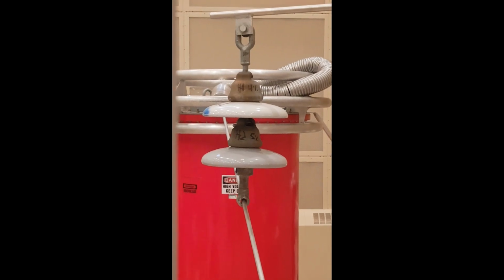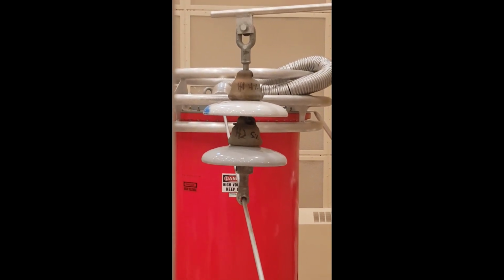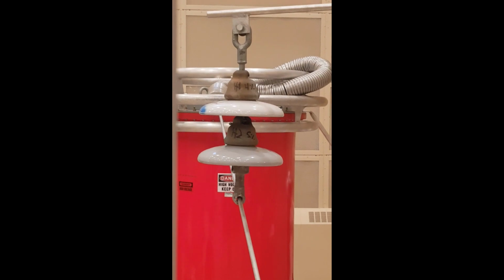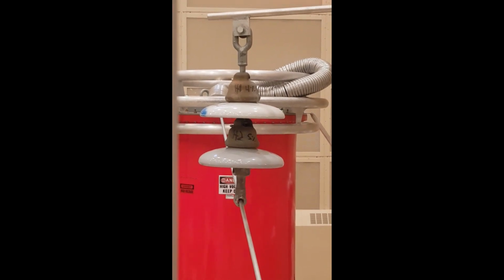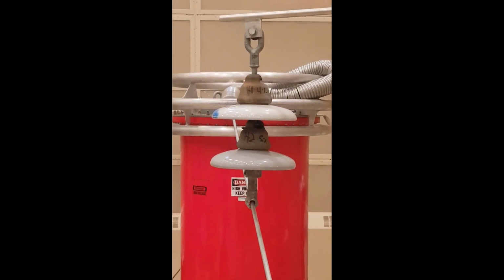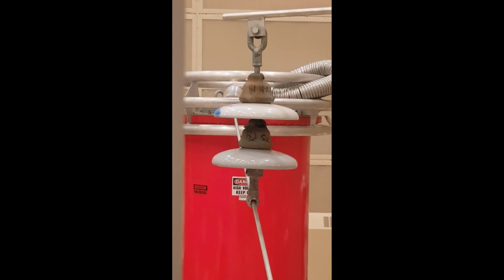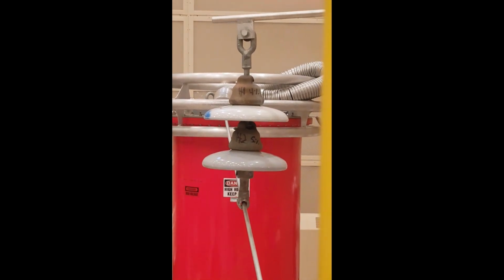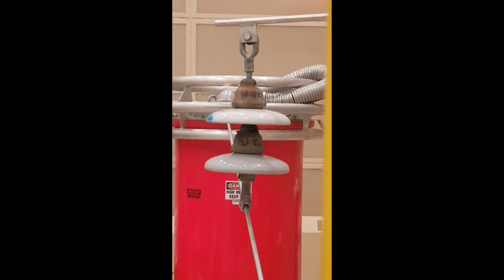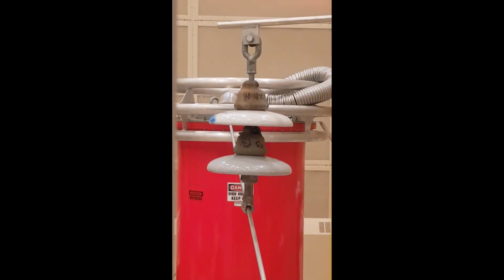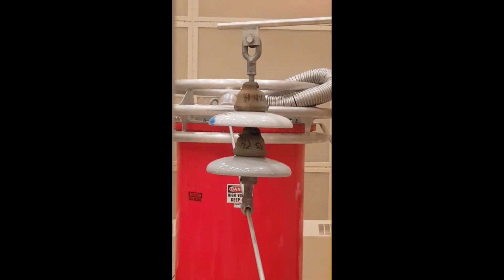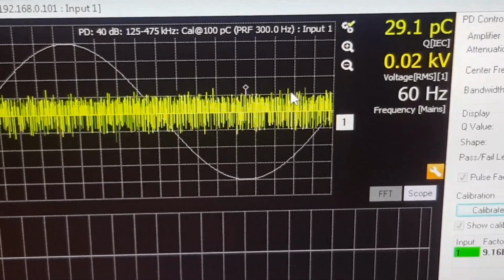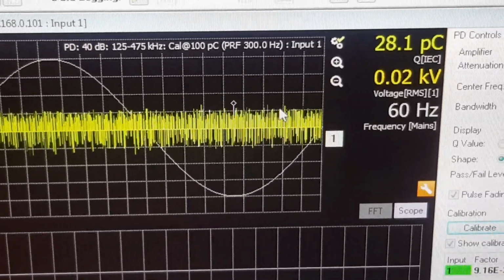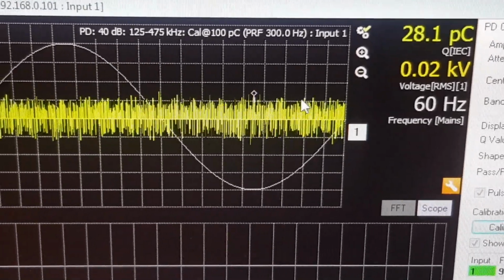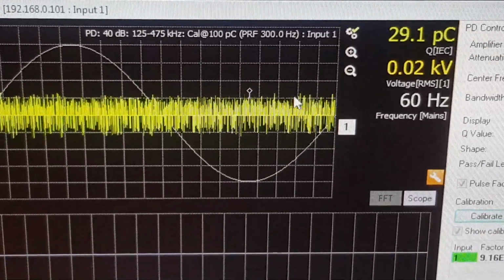In this video, we'll try to detect internal defects in outdoor insulators using non-intrusive techniques. So the first thing we'll do here in this experiment is test two discs, both of them healthy, to show that there is no partial discharge coming from this configuration. This is the PD detector at no voltage. As you can see, we have around 30 picocoulomb. So this is the background noise.